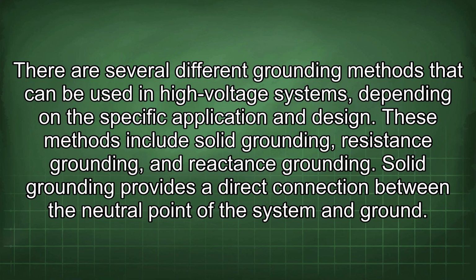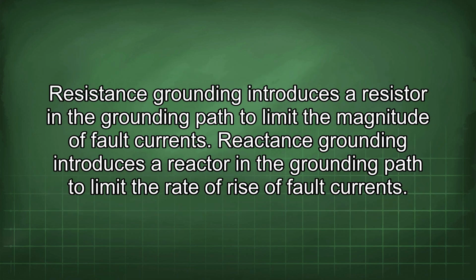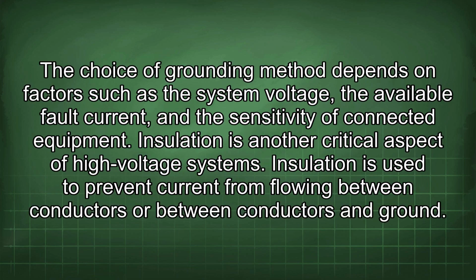Solid grounding provides a direct connection between the neutral point of the system and ground. Resistance grounding introduces a resistor in the grounding path to limit the magnitude of fault currents. Reactance grounding introduces a reactor in the grounding path to limit the rate of rise of fault currents. The choice of grounding method depends on factors such as the system voltage, the available fault current, and the sensitivity of connected equipment. Insulation is another critical aspect of high-voltage systems.